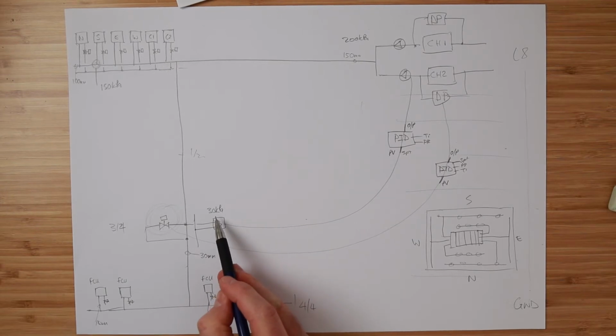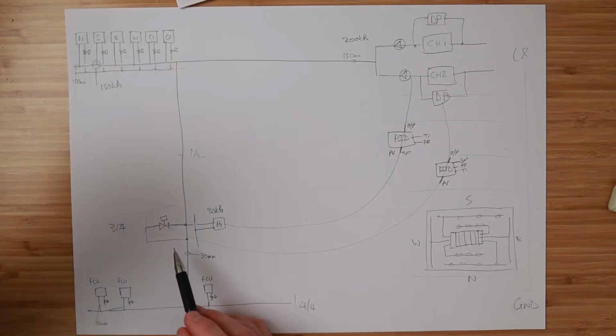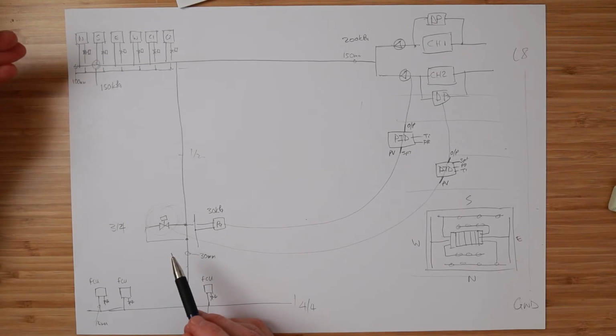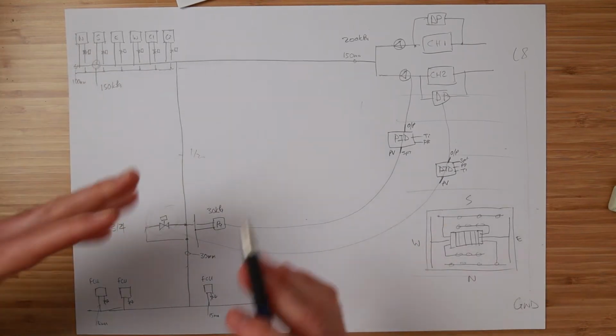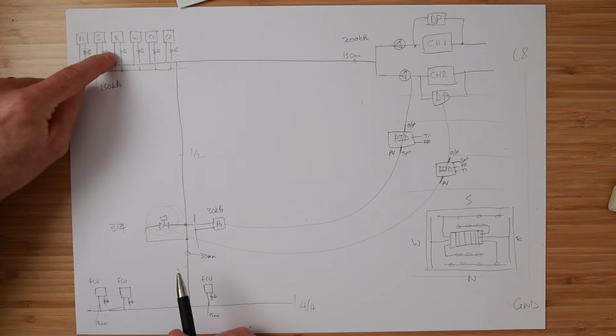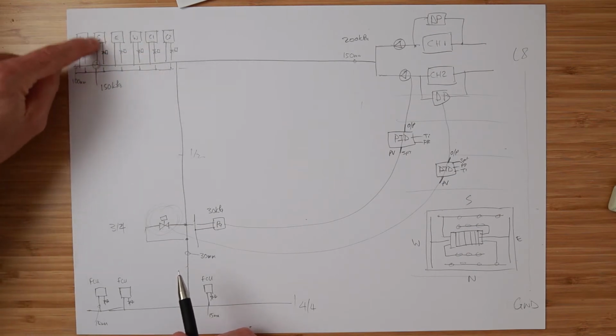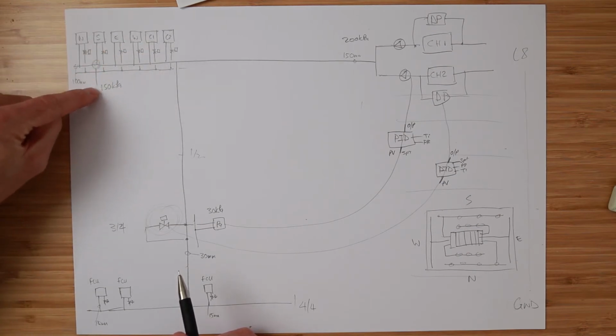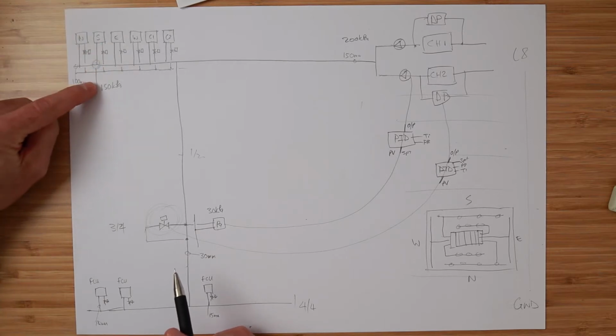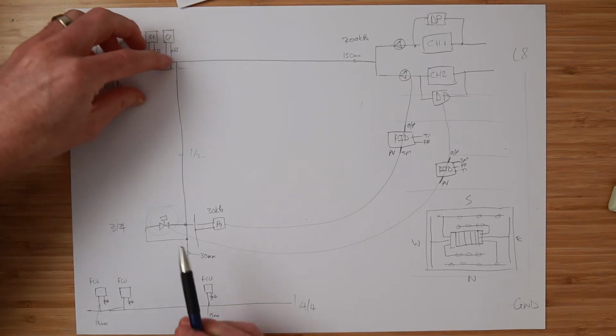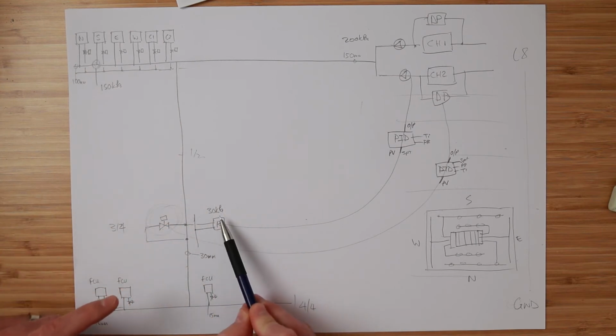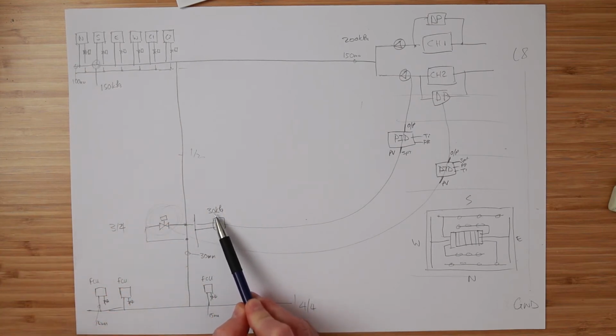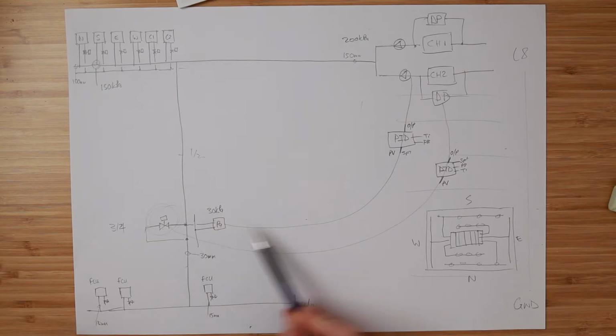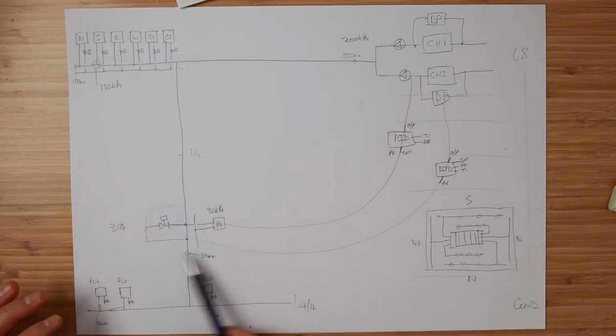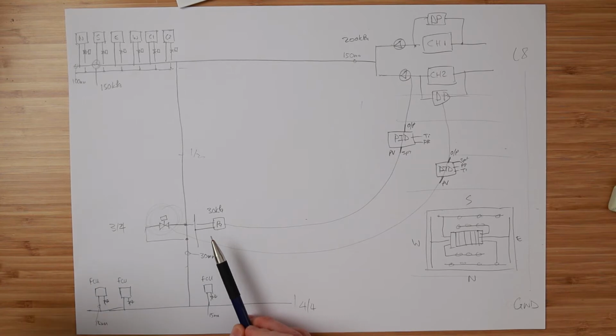This transmitter will work. This will work because as the load in the field starts to decrease and the VAVs back off and these control valves start to close off and the system pressure starts to increase here, the system pressure increases from 150, it increases up. At that point in time, that pressure increase will actually probably be detected here and the pressure will go up to 35 kPa, 40 kPa, and the pump will slow down. So putting the pressure transmitter here, the system essentially, fundamentally, will actually work.